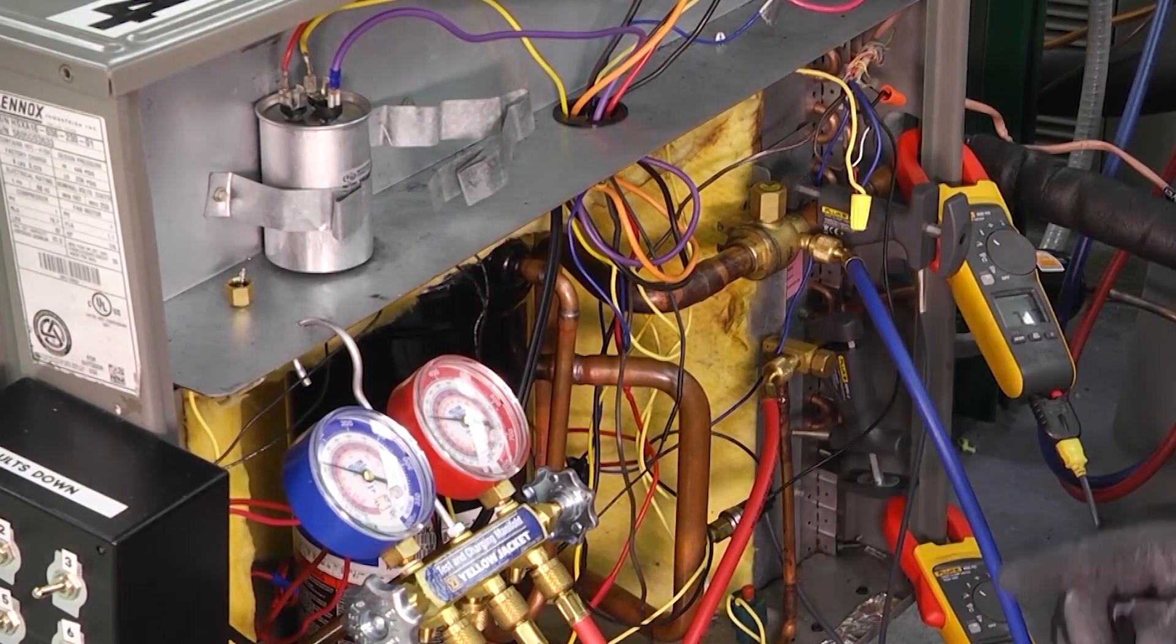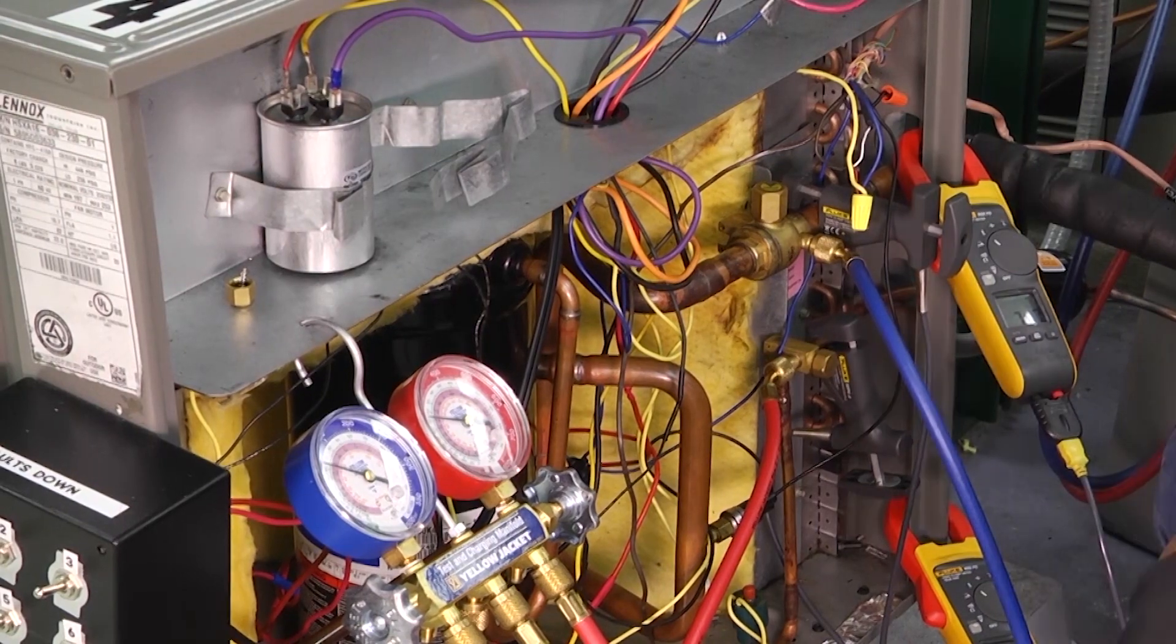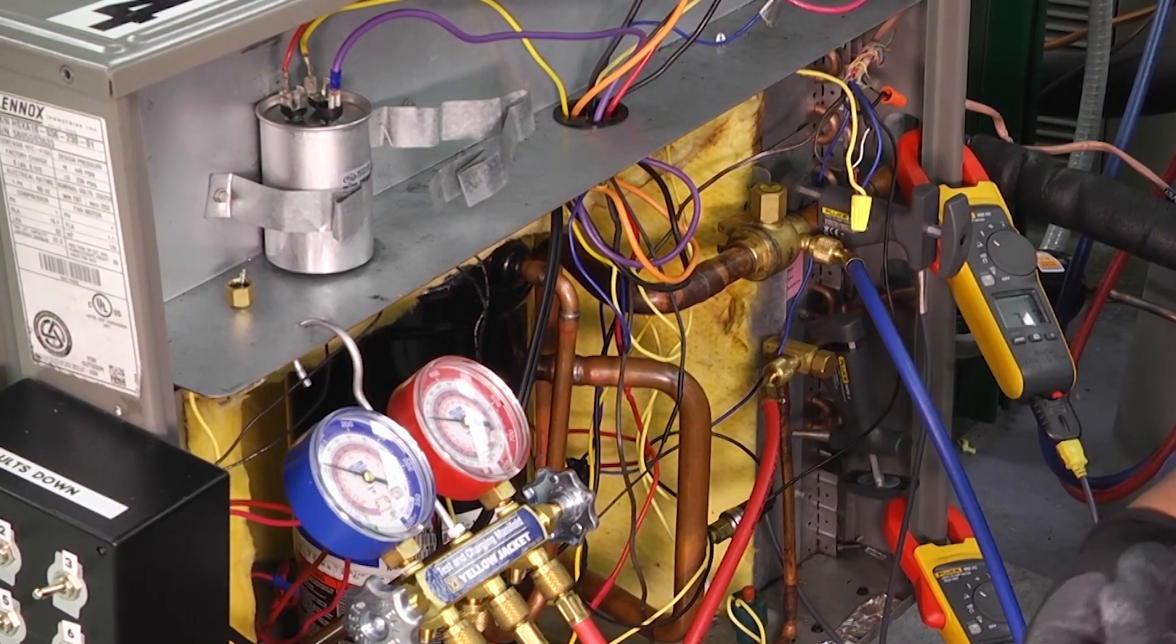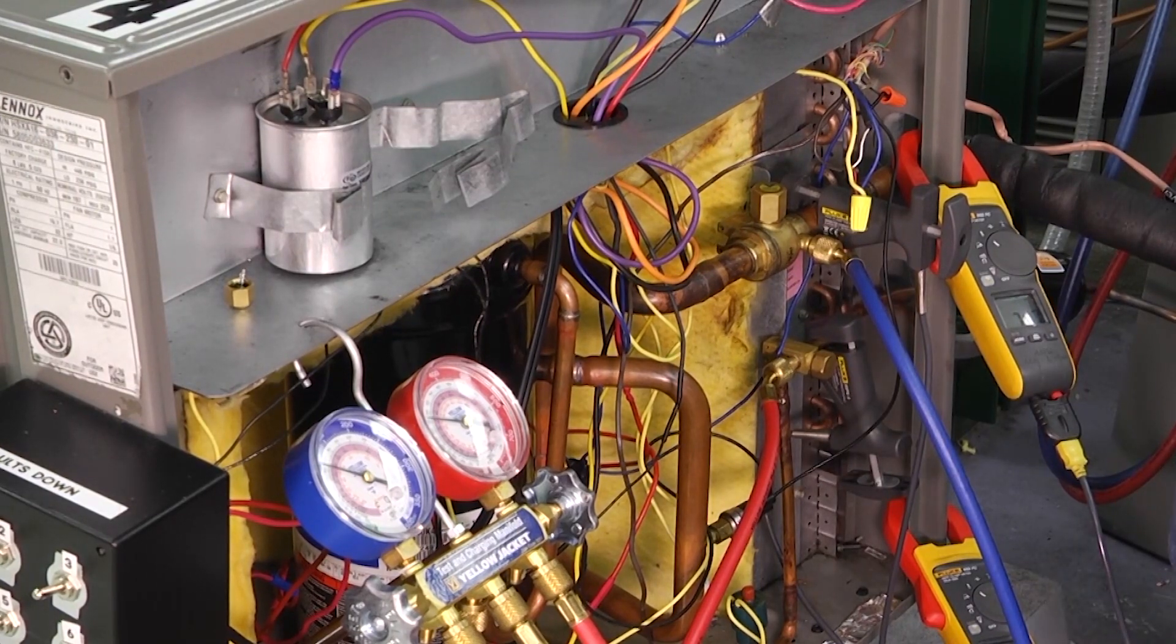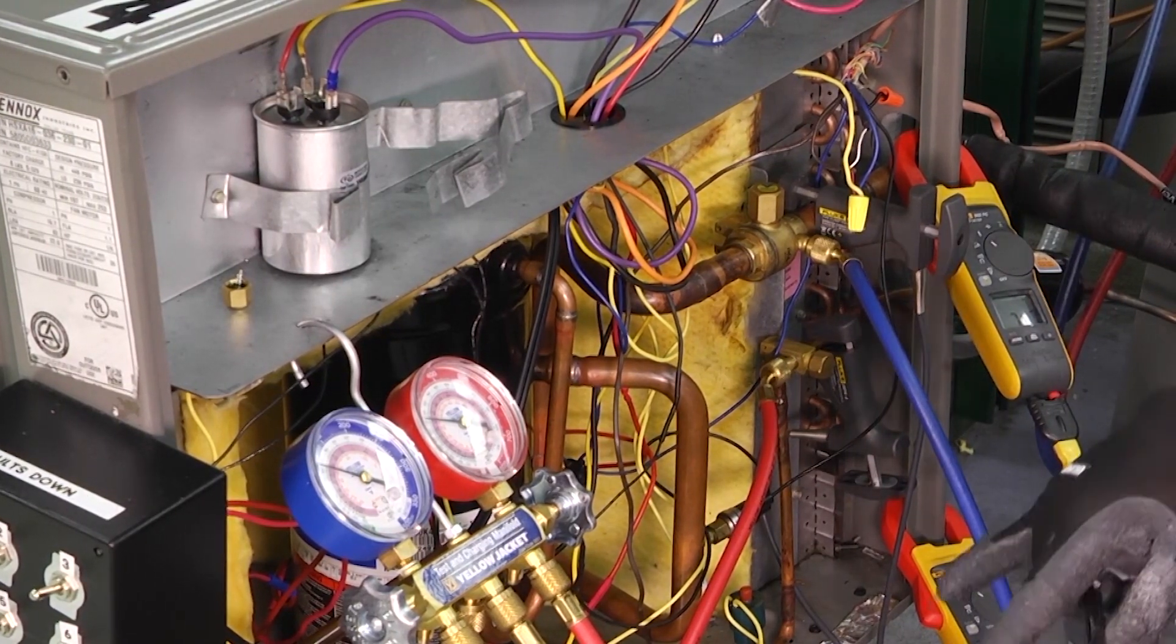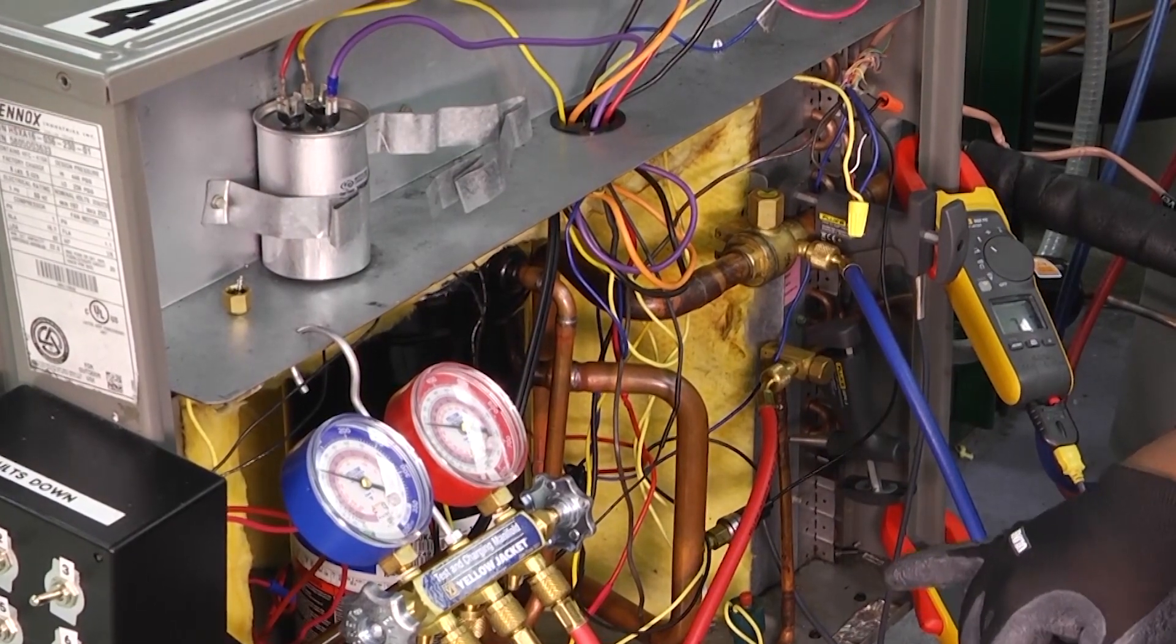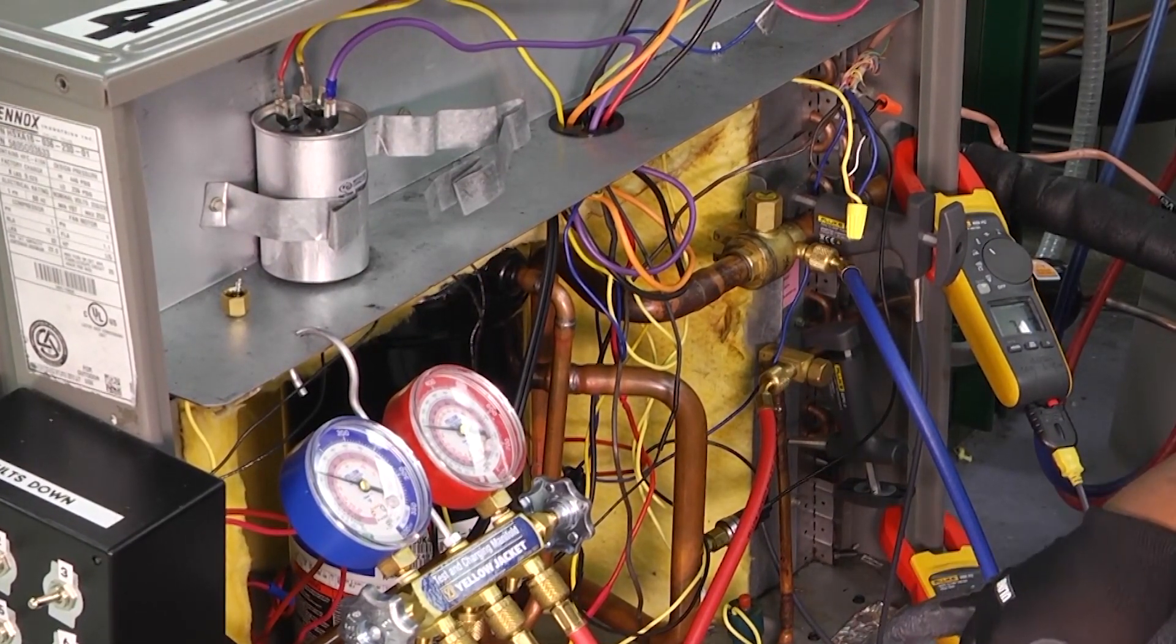It's important to understand and realize that we are not superheating until we have boiled off into a complete vapor at our evaporator coil, as we are not subcooling until we have 100% liquid inside of our condenser.